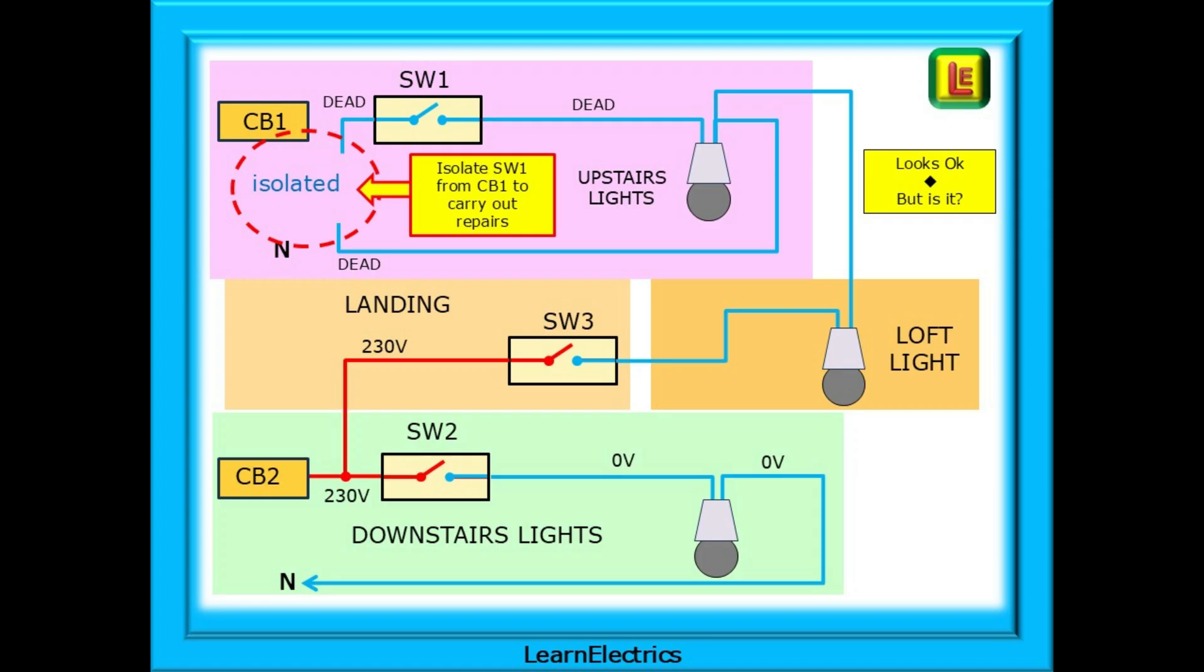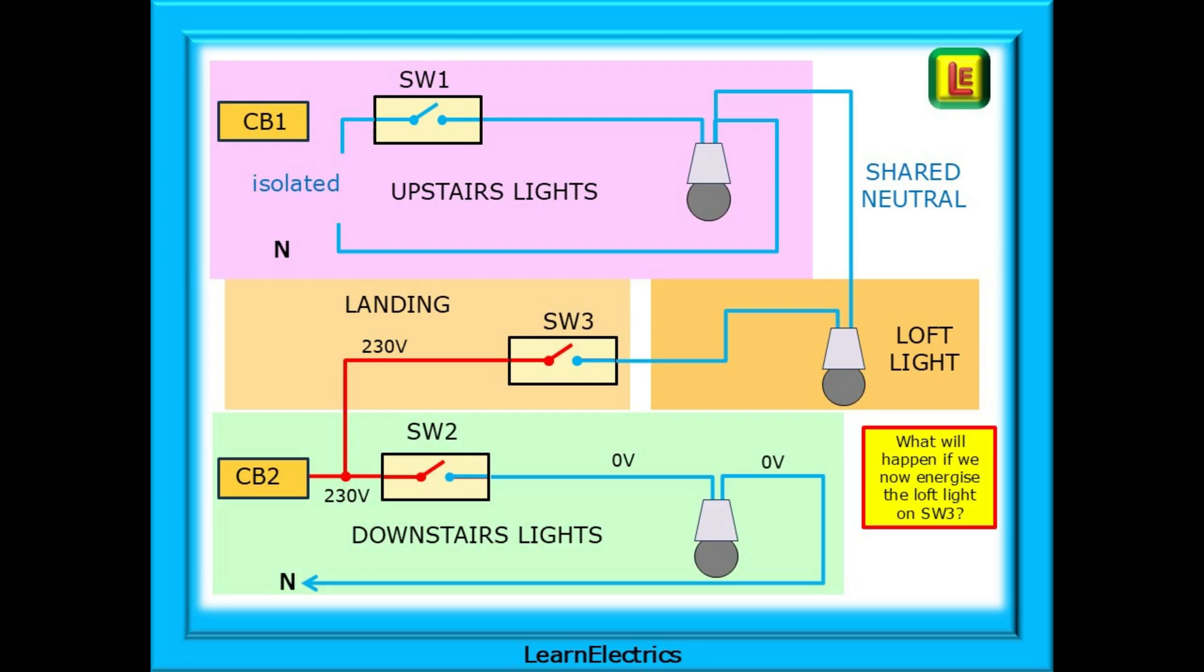Now move on a year or two and we need to carry out some work on the upstairs lighting. We isolate the circuit to SW1 by removing the line conductor from the circuit breaker number 1 and the neutral conductor from the neutral bar. Now we can start work. It all looks OK. But is it? What will happen if we, or someone else, now energises the loft light on SW3? What influence on our safety will the shared neutral have? Are we going to be safe working on the upstairs lighting, unaware of this shared neutral?